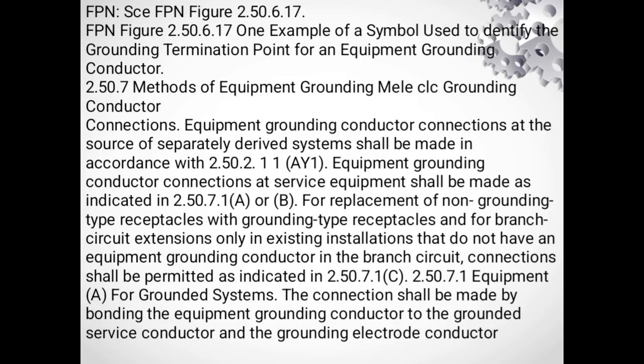2.50.7 Methods of equipment grounding conductor connection. Equipment grounding conductor connection at the source of the separately derived system shall be made in accordance with 2.50.2.1. Equipment grounding conductor connection at service equipment shall be made as indicated in 2.50.7.1 A or B. For replacement of non-grounding type receptacles with grounding type receptacles, and for branch circuit extensions only in existing installations that do not have an equipment grounding conductor, a branch circuit connection shall be permitted as indicated in 2.50.7.1 C. 2.50.7.1 Equipment. A. For a grounded system, that connection shall be made by bonding the equipment grounding conductor to the grounded service conductor and the grounding electrode conductor.